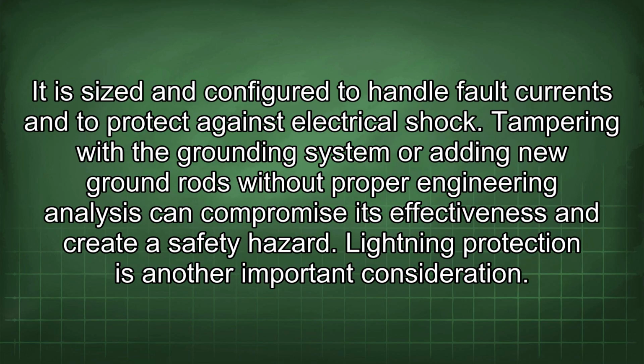It is sized and configured to handle fault currents and to protect against electrical shock. Tampering with the grounding system or adding new ground rods without proper engineering analysis can compromise its effectiveness and create a safety hazard. Lightning protection is another important consideration.